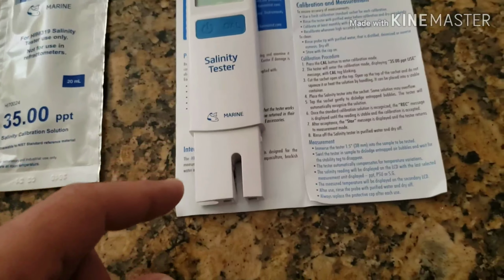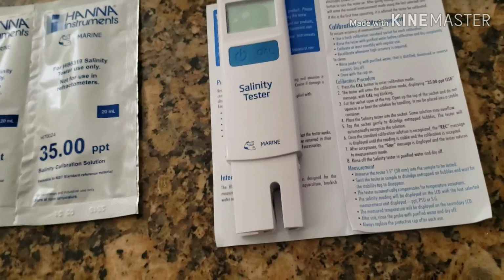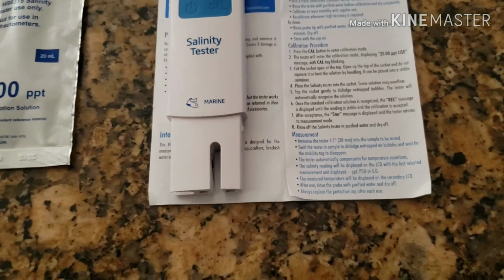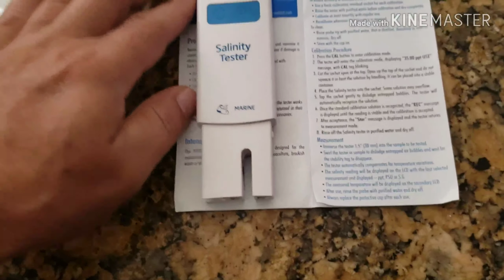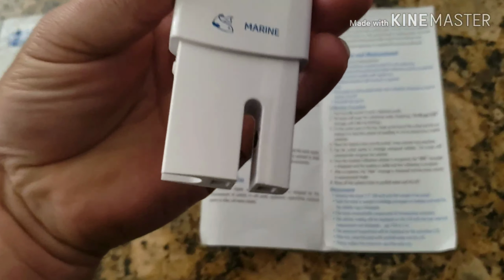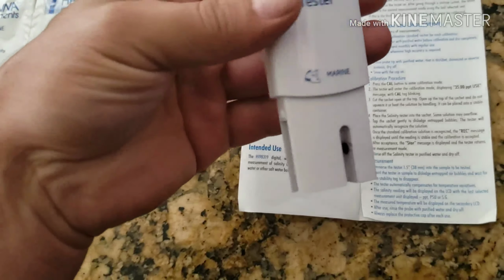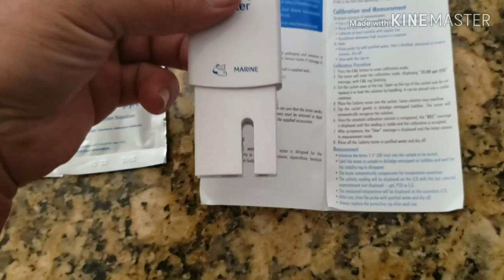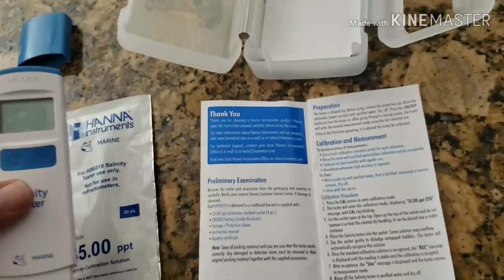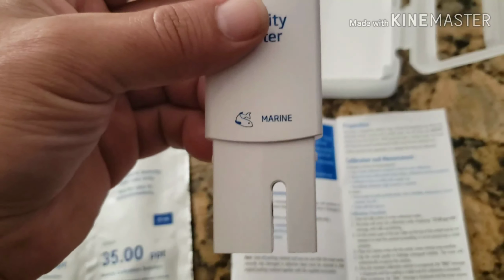Do not use tap water. There's chloramines, fluorides, and stuff that could damage the probe over time. So best to stick by recommended rinsing procedures and use RO DI water or distilled water if RO DI is not on hand, just to keep your tester in tip-top shape. So before calibration and after every use.